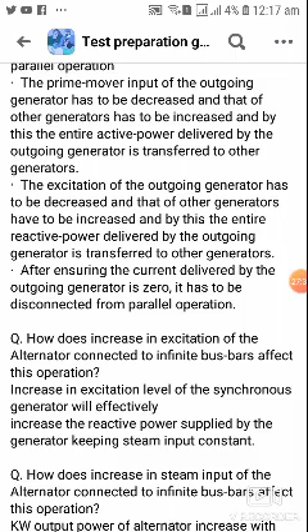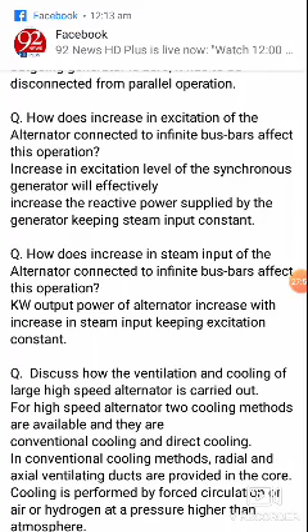Question number 50. How does increase in excitation of the alternator connected to infinite bus bar affect this operation? Increase in the excitation level of the synchronous generator will effectively increase the reactive power supplied by the generator, keeping steam input constant. Question number 51. How does increase in steam input of the alternator connected to infinite bus bar affect this operation? kW output power of alternator increases with the increase in steam input, keeping excitation constant.